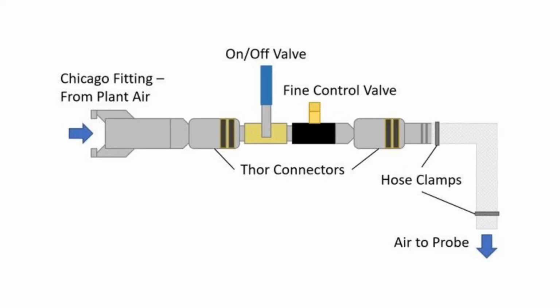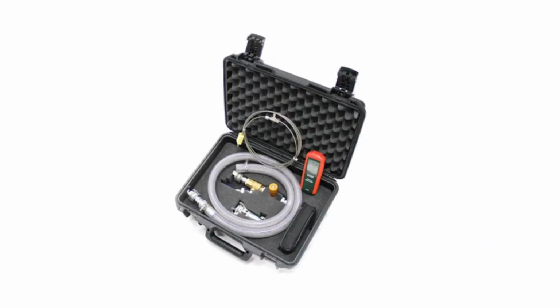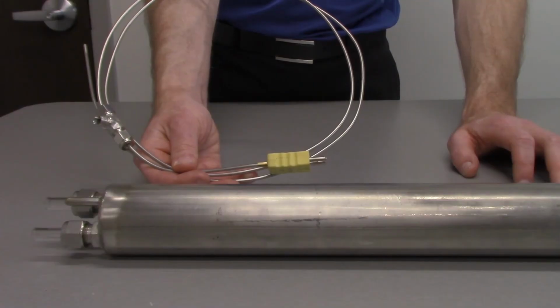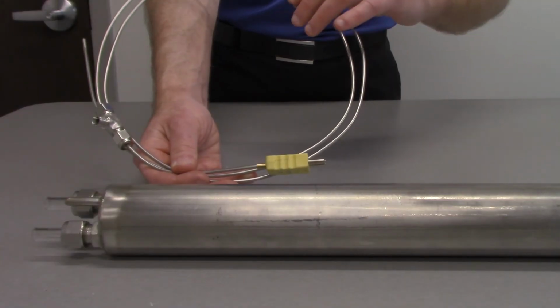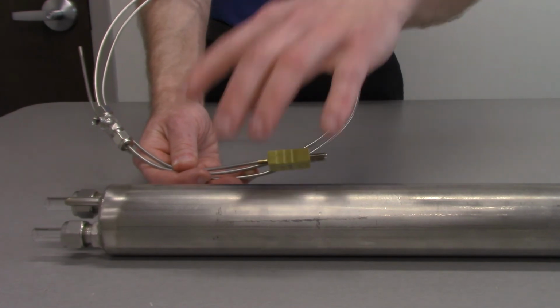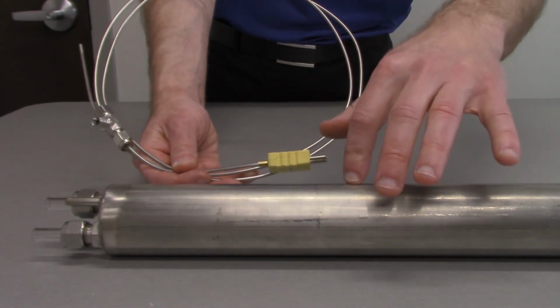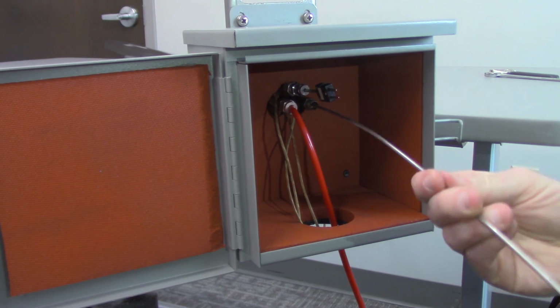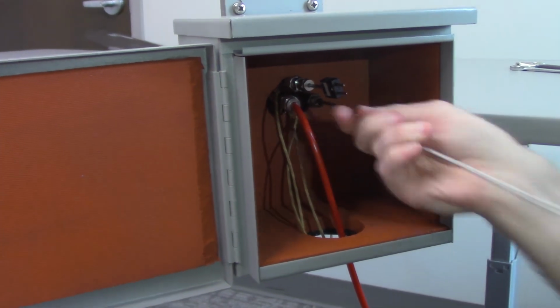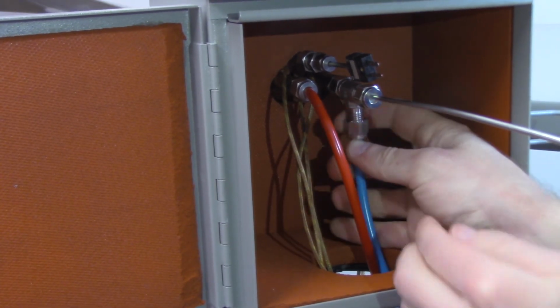The fine temperature control kit contains a few components, including a Chicago fitting to connect to plant air, valves, a low-pressure air hose, and an inline thermocouple. Many sorbent trap applications require the traps to be maintained in a narrow range of temperatures, and this kit gives the operator the means to do so. The inline thermocouple provides the most accurate measurement of trap temperature possible because the end of the thermocouple rests inside the trap liner immediately behind the trap. It is inserted through the back of the probe liner like this, and then secured to ensure a leak-proof connection.